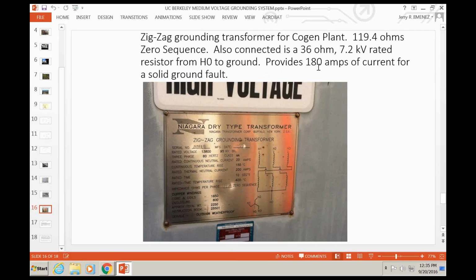That provides us about 180 amps of current for a solid ground fault, which, so far in my time here, every ground fault we've had has been. We haven't had any real arcing, or if they arc, it's not for very much time, maybe just a few milliseconds, and then it becomes a good ground fault. Or you mean your phase-to-phase will quickly turn to solid ground?